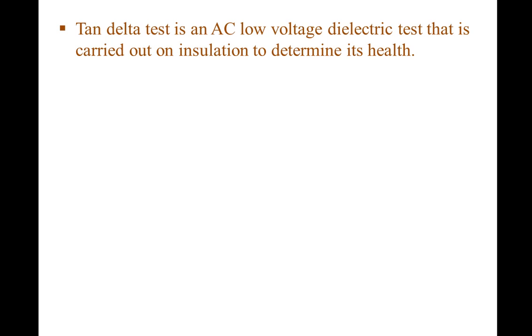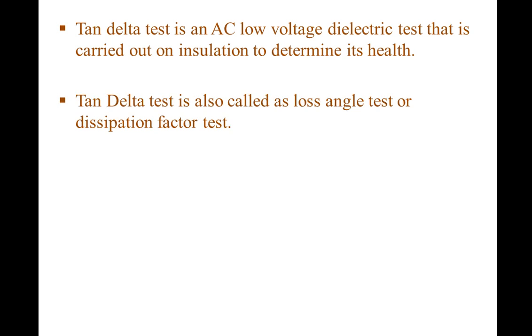Tan delta test is an AC low voltage dielectric test that is carried out on insulation to determine its health. It is carried out on various electrical equipment such as current transformers, potential transformers, coupling capacitors, CVTs, transformer bushings, and transformer windings. Tan delta test is also called as loss angle test or dissipation factor test.